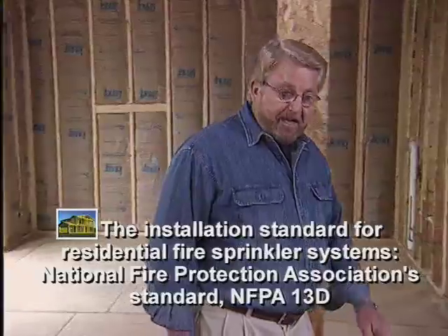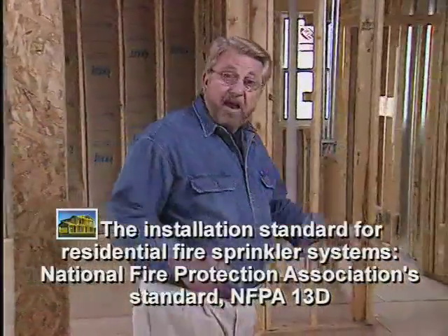The national standard for home fire sprinklers is the National Fire Protection Association standard, NFPA 13D. Now, the standard is intended primarily to save lives, but it can also dramatically reduce property damage. The goal is to provide 10 minutes of sprinkler water on a fire to allow the occupants to escape and the fire department to respond.